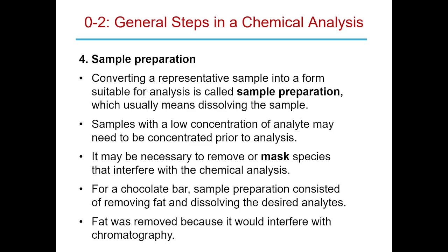Solid samples are more difficult to manipulate, but you can. And gas samples need to be made essentially where you're going to test them, because they're just horrible to try to keep and use, okay? I did a lot of stuff with gas samples, by the way. They are doable. They have a lot of mechanics that are similar to liquid samples, but you have to have very specialized, very expensive, tens of thousands of dollars pieces of equipment to deal with them, okay? It's very pricey, very difficult.